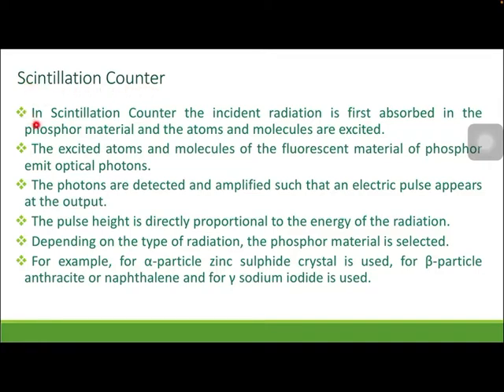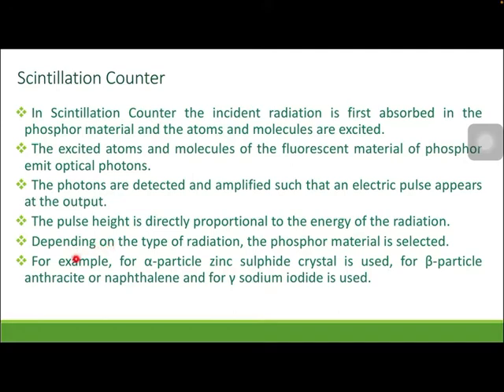In the scintillation counter, the incident radiation is first absorbed in the phosphor material and the atoms and molecules are excited. The excited atoms and molecules of the fluorescent material of phosphor emit optical photons. The photons are detected and amplified such that an electric pulse appears at the output. The pulse height is directly proportional to the energy of the radiation, so in this you can find out the energy also.